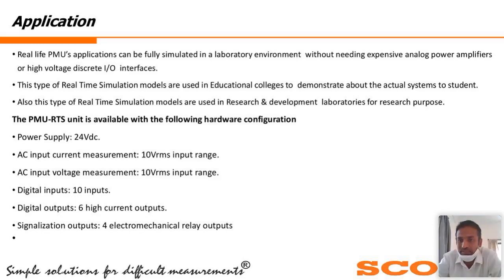In the substation, we have CT of 1 ampere and PT of 110. What is your recommendation on the CT core, metering or protection? Again, that's what I'm saying. You go for the metering core, because the protection core is already being used for protection purposes, so the metering core can be an easy way to connect to the PMU.